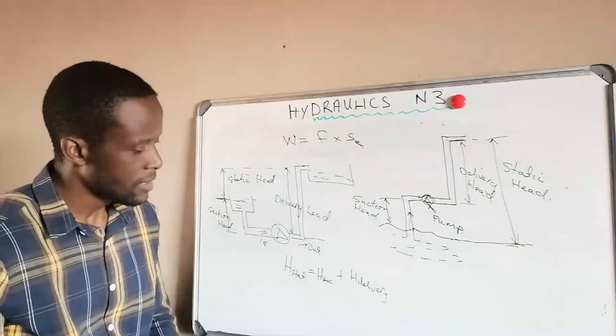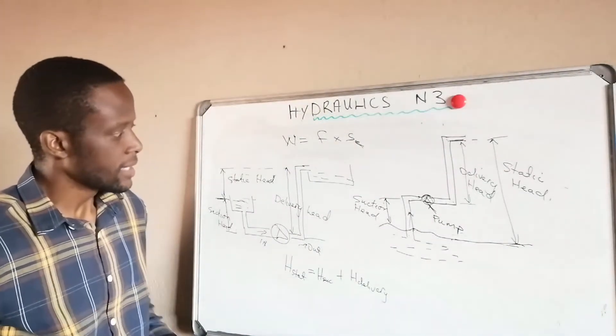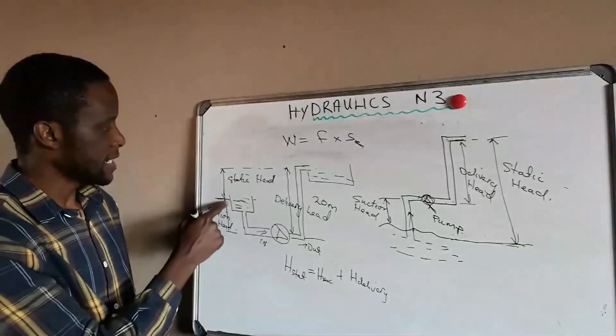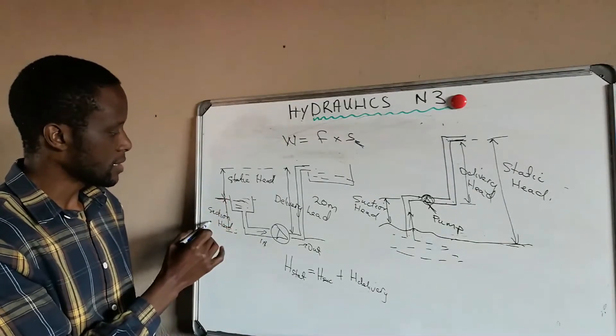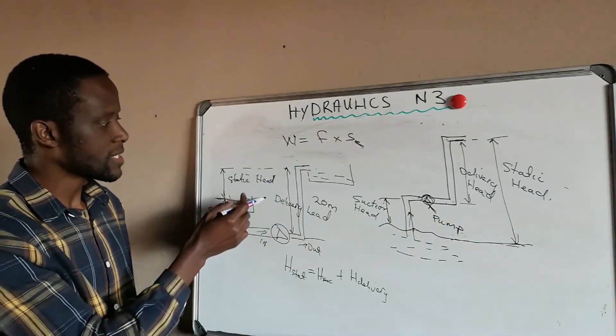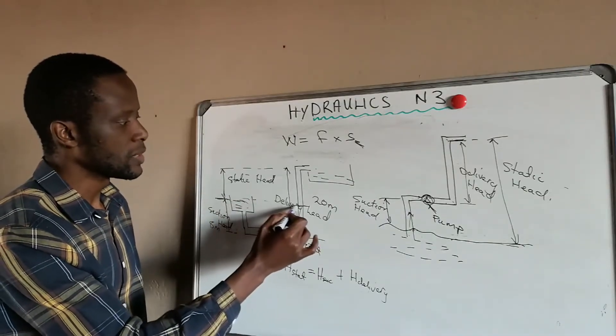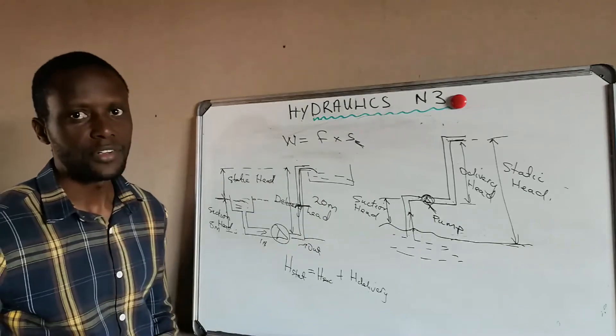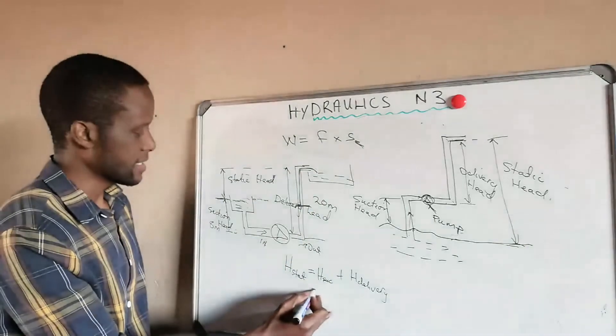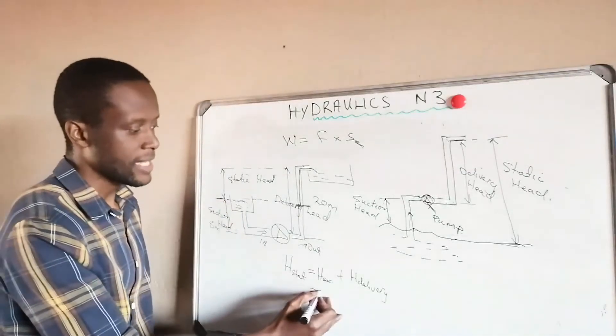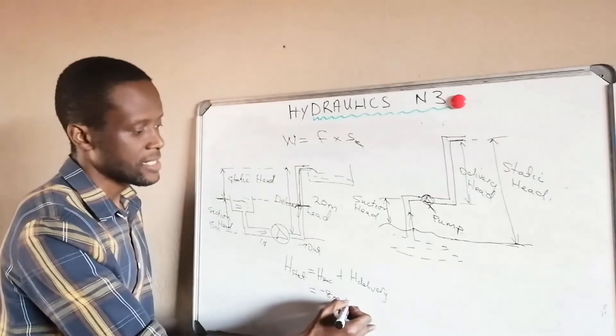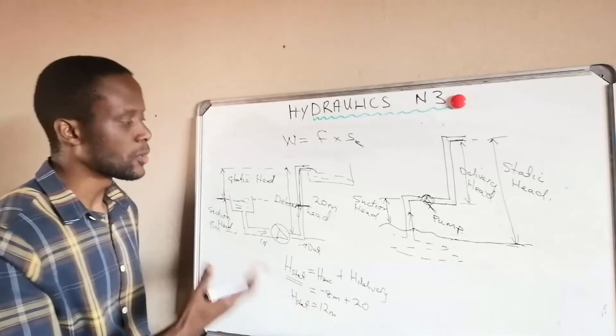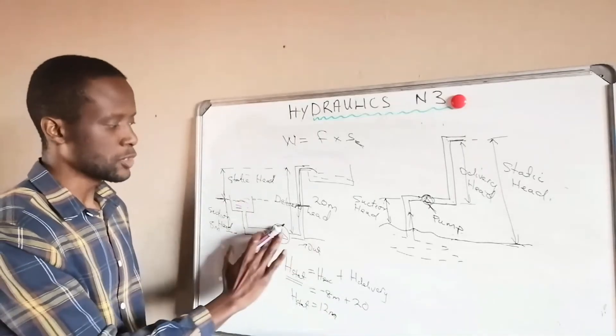For example, if in the diagram the delivery head is 20 meters and the suction head is 12 meters, the static head equals suction head plus delivery head. However, in a case where the water source is at a suspended height above the pump — with a suction head of negative 8 meters and delivery head of 20 meters — the static head equals negative 8 plus 20, which equals 12 meters.